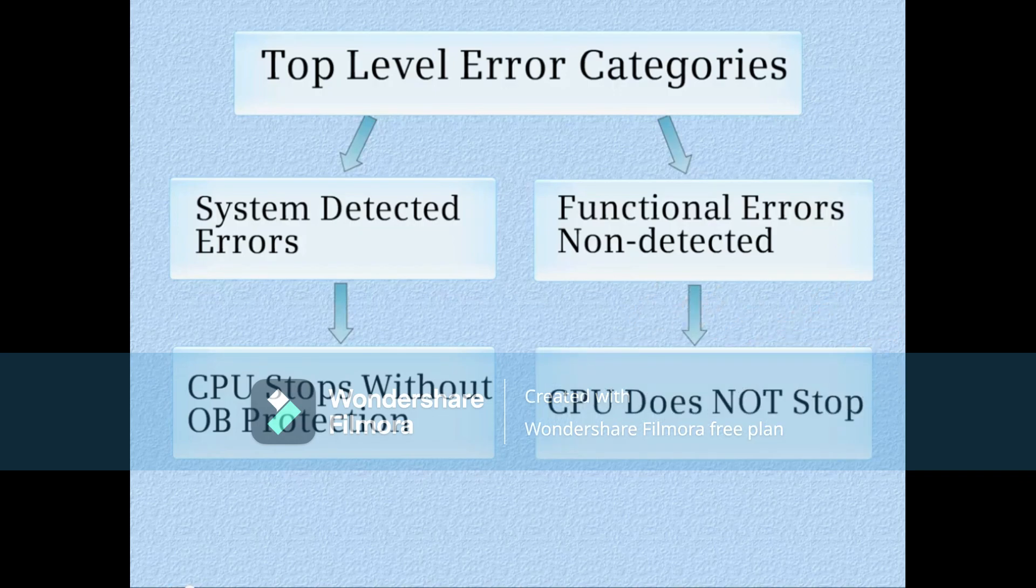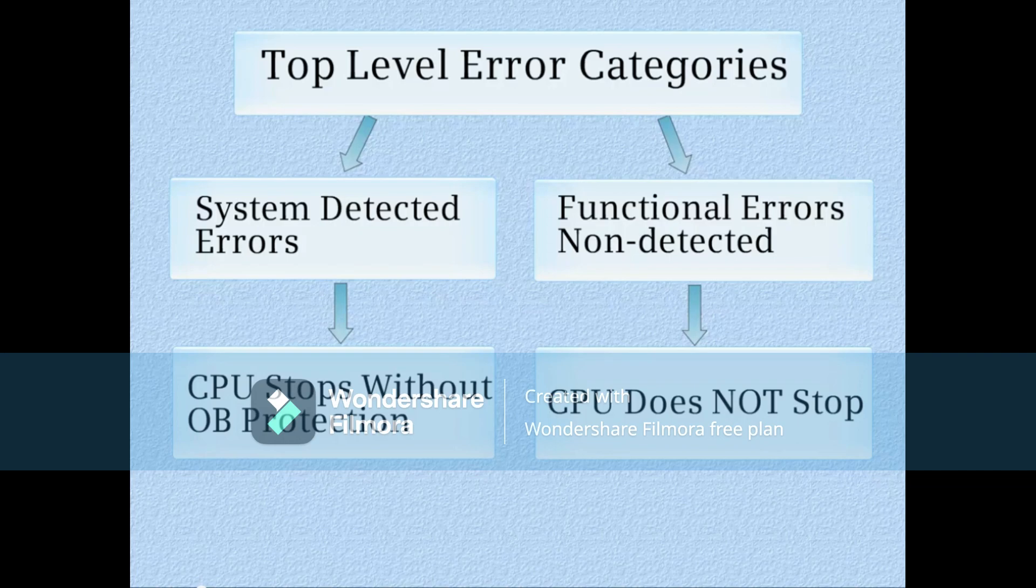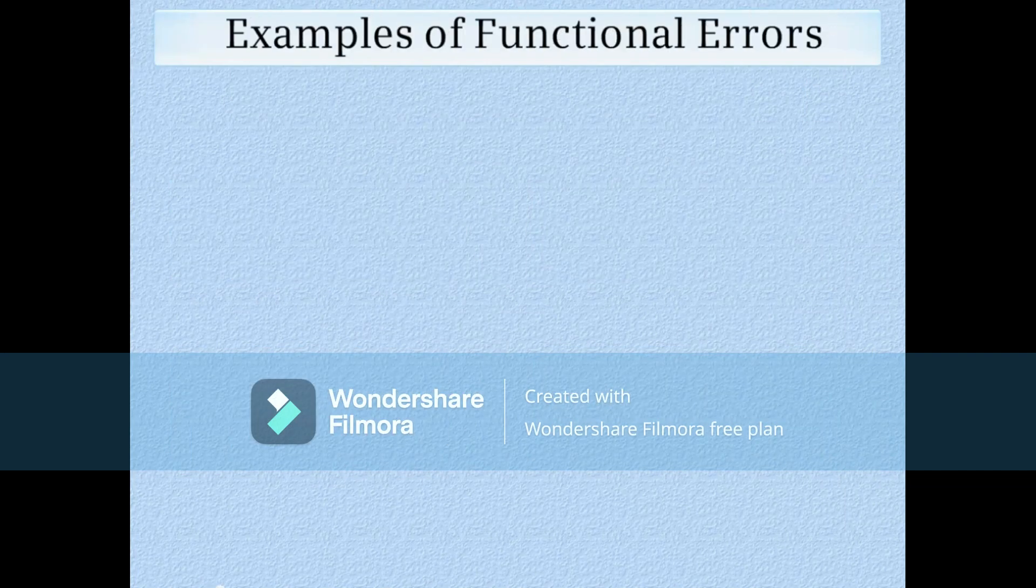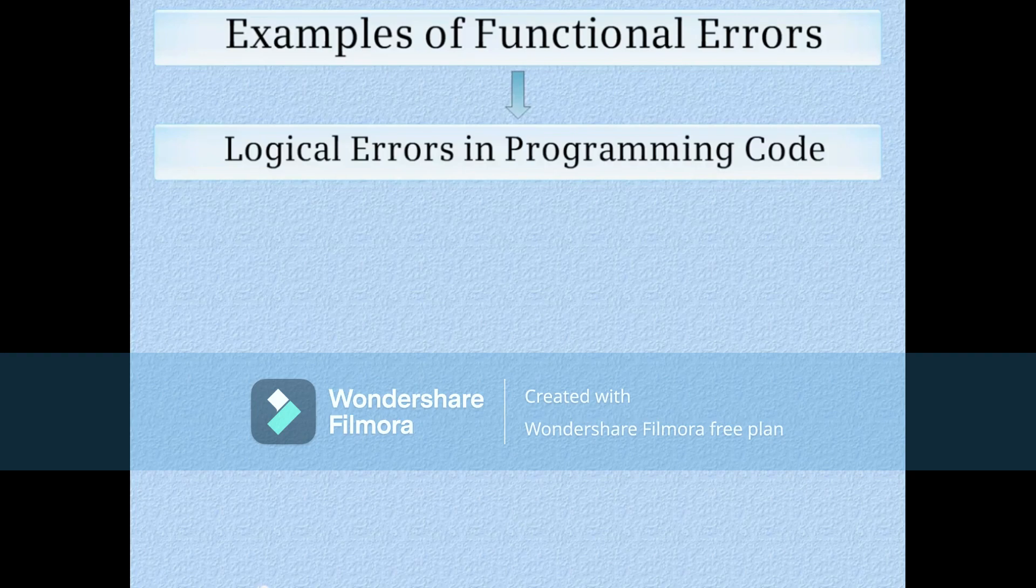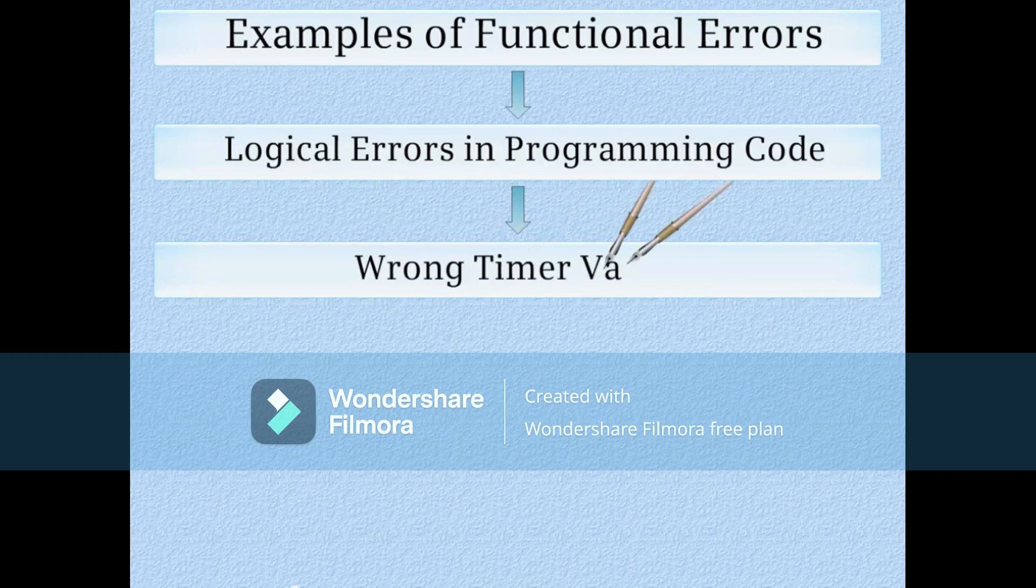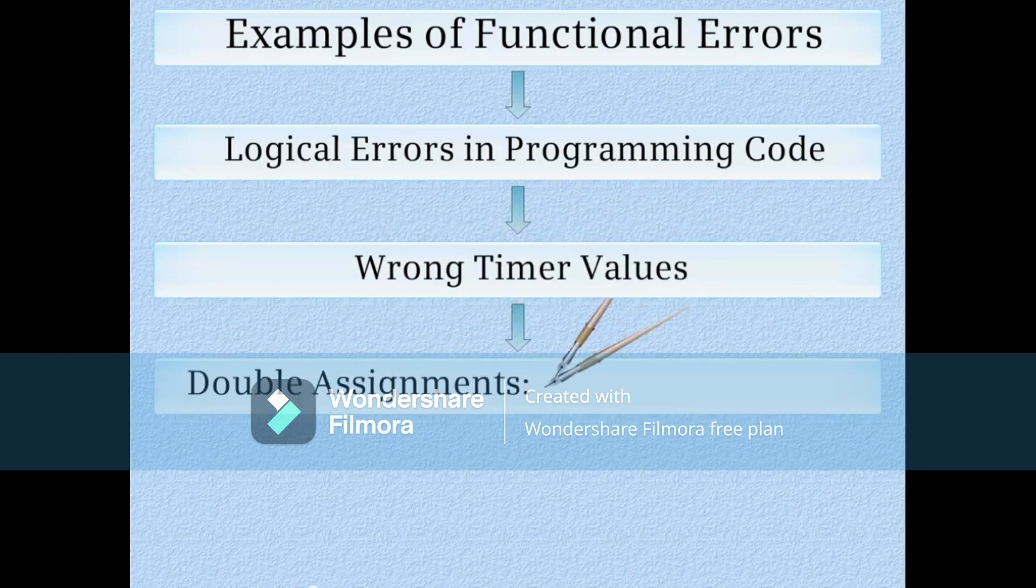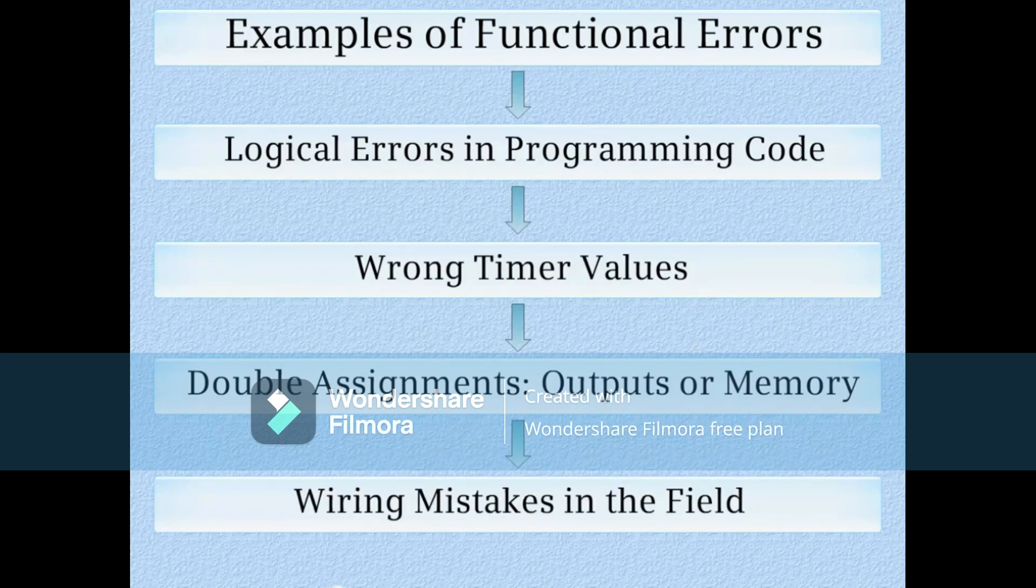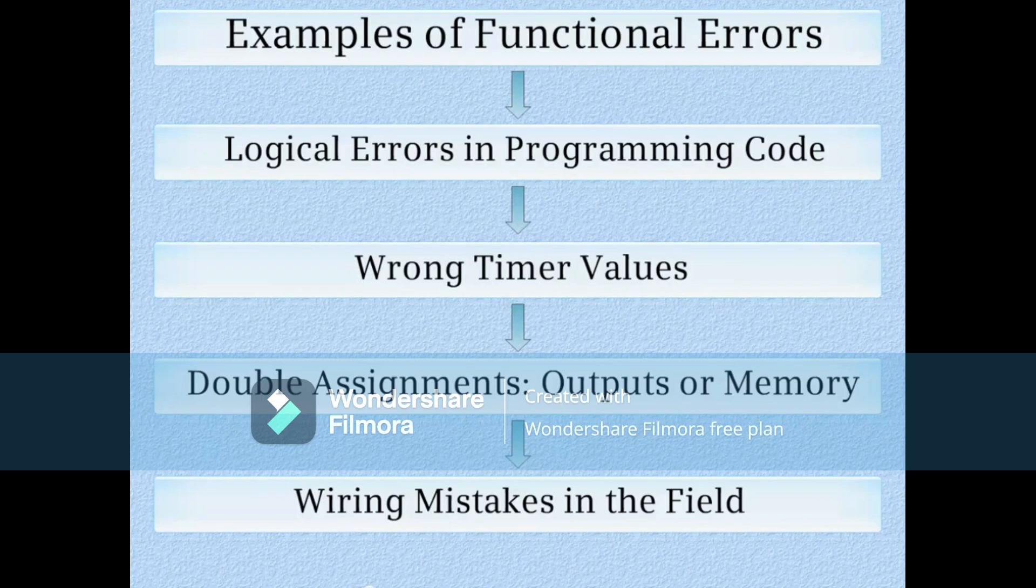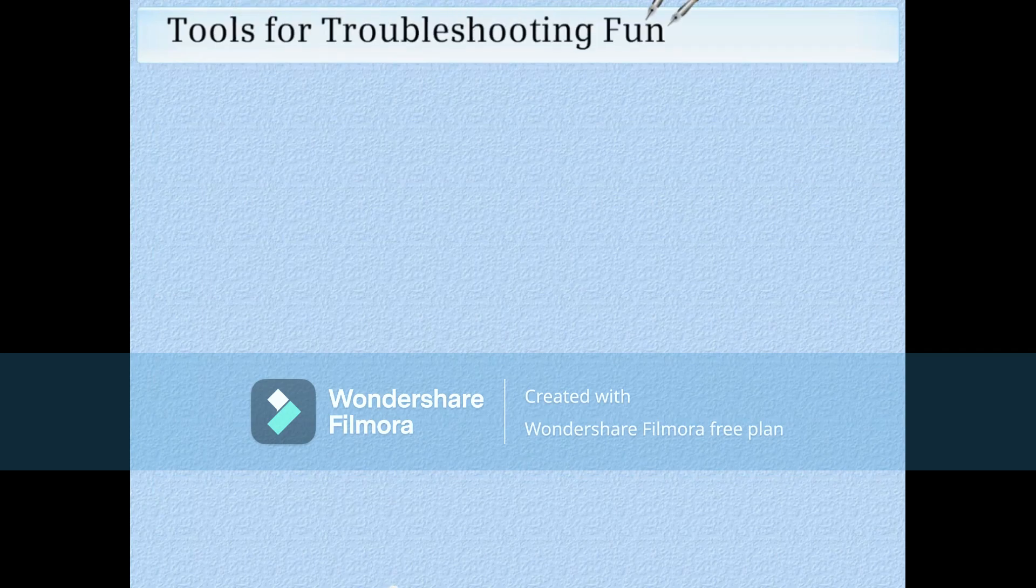Let's now talk about functional errors. Some examples of these are logical errors in the programming code, for example using a normally open contact where a normally closed contact should have been used, supplying the wrong value to a timer, writing to an output or memory bit more than once, or wiring mistakes that were made in the field. All of these will cause the system to operate incorrectly but the PLC is not able to detect the problem.